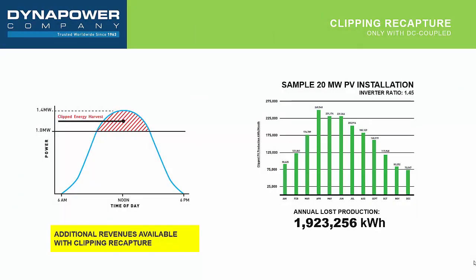We mentioned before that there are a couple of advantages from a revenue perspective of going DC coupling, and probably the biggest one, and the one that's most well understood, is clipping recapture. So this is a phenomenon, of course, where the DC PV array sizing is oversized relative to the maximum AC output of the PV inverter. And this, of course, results in situations during the day when there is excess DC capacity from the PV array that cannot be utilized by the PV inverter. This is, of course, the clipped energy as demonstrated on the graph on the left.